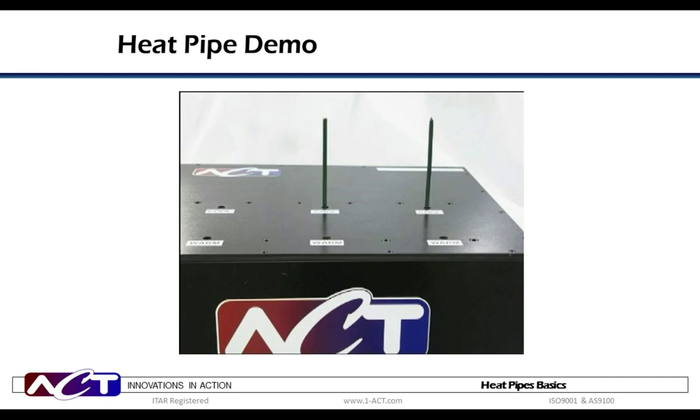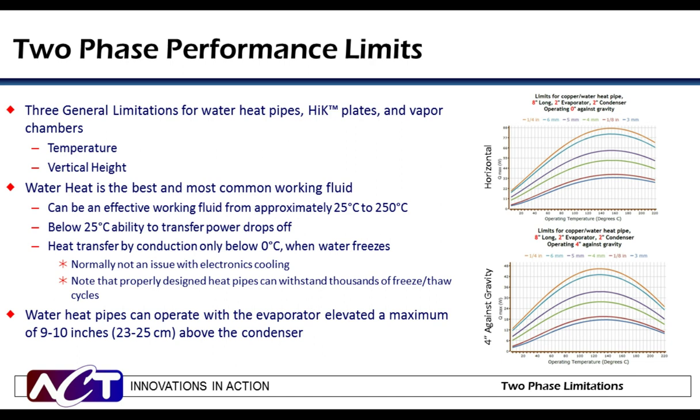Quite a difference between the two. Of course, there are performance limitations for any device, and that certainly includes heat pipes, HiK plates, and vapor chambers. Key factors that must be considered are temperature, as this will determine the appropriate working fluid, and height against gravity of the evaporator versus the condenser, as this will be important for wick material and design. Water is the best and most commonly used working fluid. Water can be used from approximately 25 degrees C to almost 250 degrees C, well beyond its nominal boiling point.